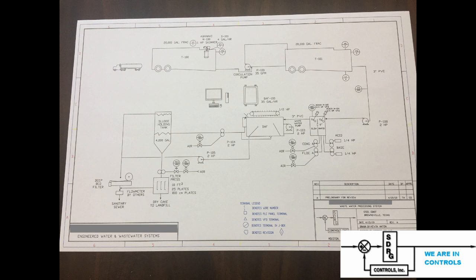The next thing to do was to develop a process diagram for this specific operation. This was a P&ID, which shows the process and instrumentation. It shows all the materials coming into the facility and all of the outflows, such as the dry cake going to a landfill and discharge going to the sanitary sewer. It also shows the computer that was logging data for all the various parameters.